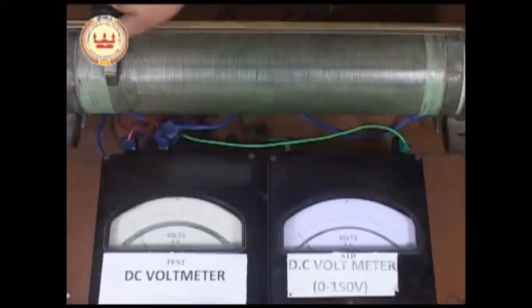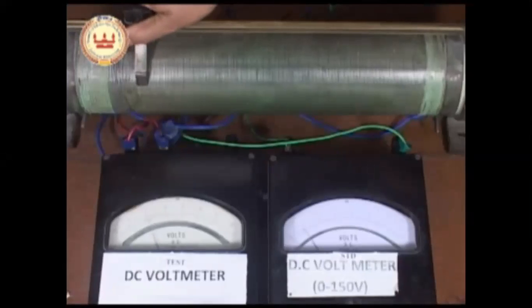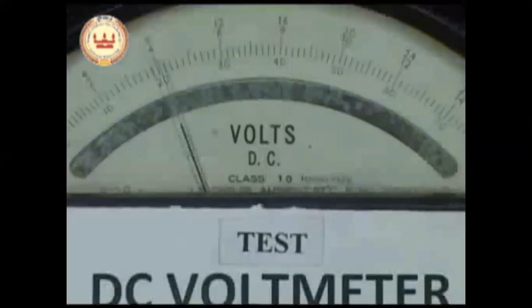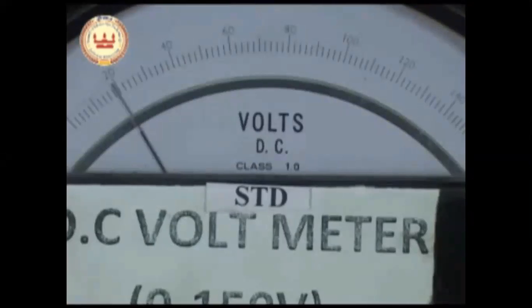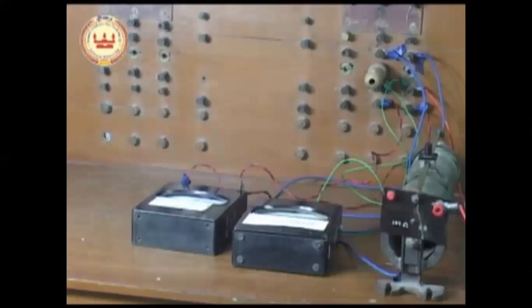In a similar way, by varying the rheostat, we can cover the entire range of the test voltmeter, and at different readings of the test voltmeter, the corresponding readings of the standard voltmeter should be noted. Thus, the experimentation is completed for calibration of voltmeter. Okay, so this is the complete video we have for this procedural part.